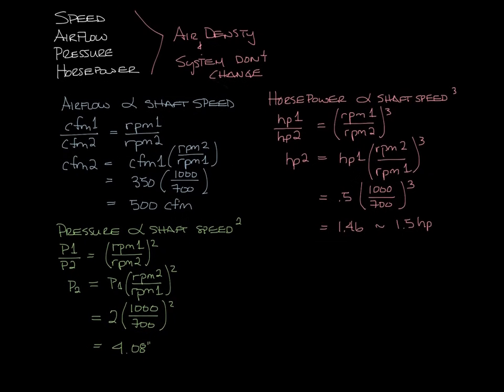So let's bring them all back on the screen. So the first fan law is that the airflow is proportional to the shaft speed. The second fan law is that pressure is proportional to the shaft speed squared. And the third is that horsepower is proportional to the shaft speed cubed.